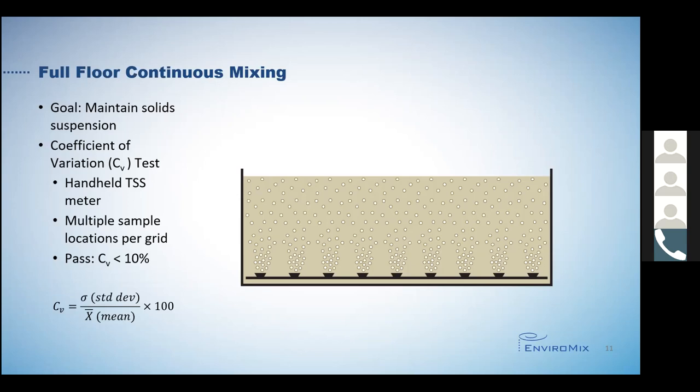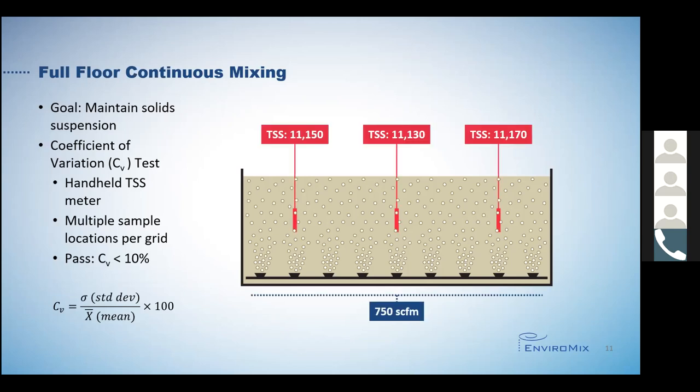For all the data I'm about to share, I'm going to be showing the mean TSS value. Each sample set of data that we collected had a corresponding CV value of less than 5% and showed complete mixing. The baseline data we collected was to confirm complete mixing in a continuously aerated tank. You can see the average TSS values in three separate areas or grids of this tank while the entire tank is aerating continuously. The air supply to the three grids was set at 750 SCFM, which is the equivalent of 30 SCFM per 1,000 cubic feet for this entire tank volume. The mean values are all within 50 milligrams per liter of each other, confirming that full floor, continuously operated aeration does indeed completely mix the tank.